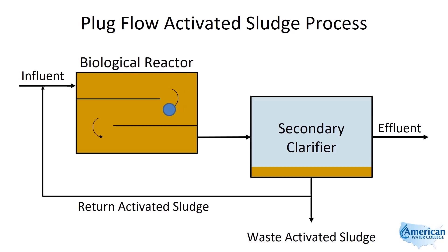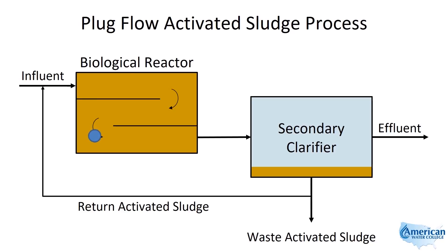This type of system is normally at least 10 times longer than it is wide. The organic load and the dissolved oxygen uptake is very high at the reactor inlet, and the aeration system must be able to transfer sufficient oxygen at this point, and then can be tapered off as the water moves through the reactor. This design provides the highest BOD removal rate per unit volume, as well as being less susceptible to sludge bulking caused by filamentous bacteria than other designs, assuming there is sufficient dissolved oxygen at the front end of the reactor.